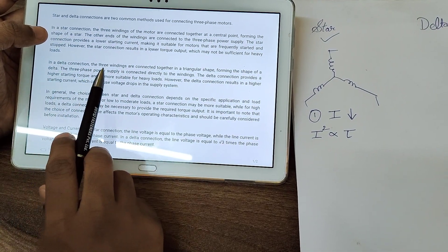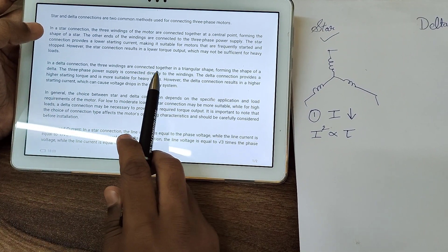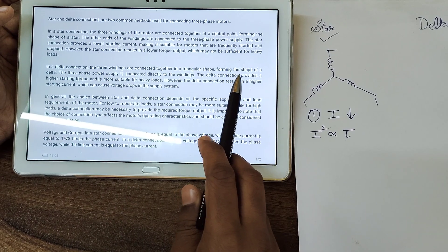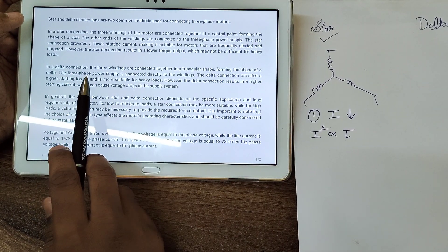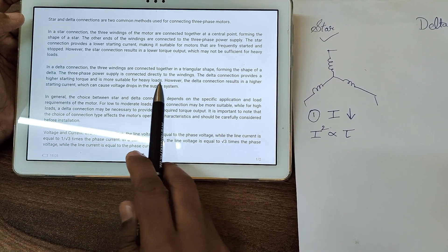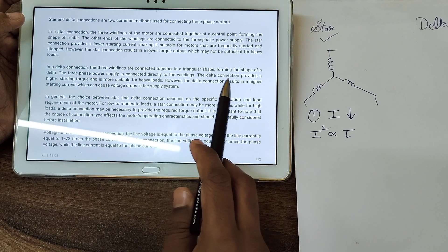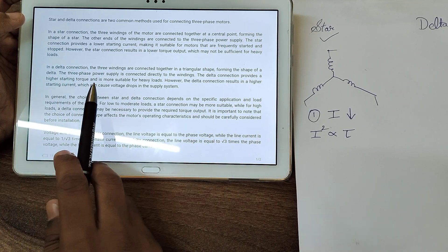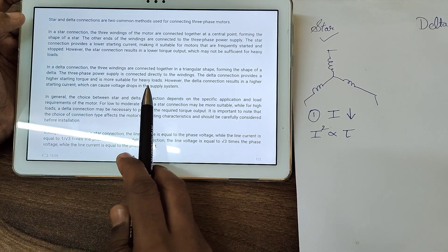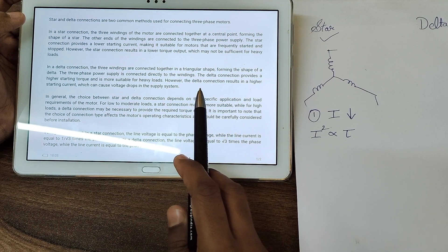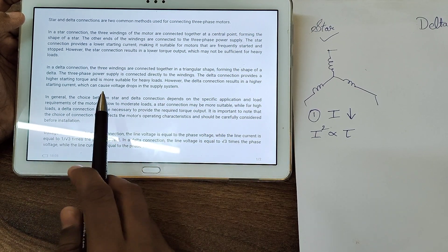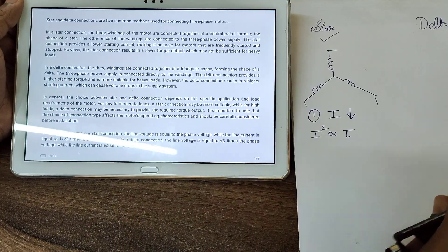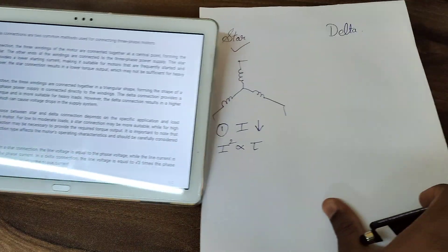In a delta connection, the three windings are connected together in a triangular shape, forming the shape of a delta. The three-phase power supply is connected directly to the windings. The delta connection provides a high starting torque and is more suitable for heavy loads. However, the delta connection results in higher starting current, which can cause voltage drops in the supply system.